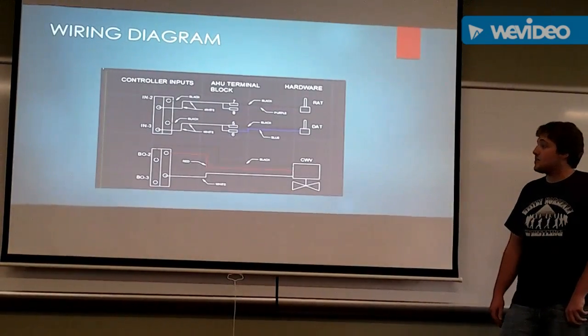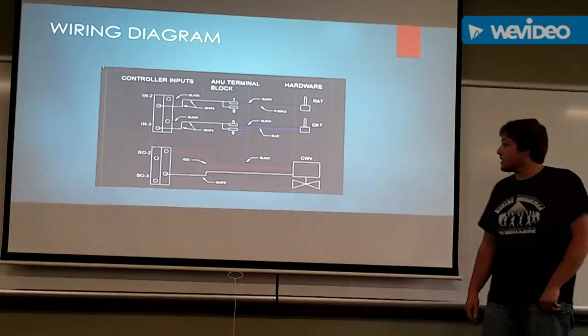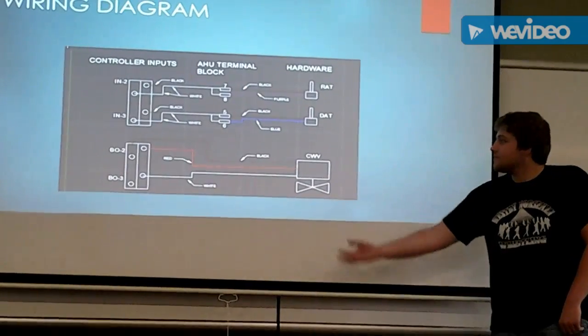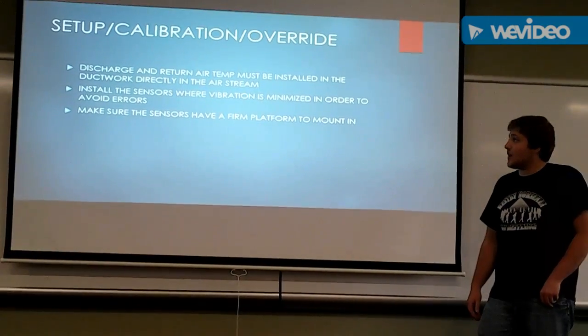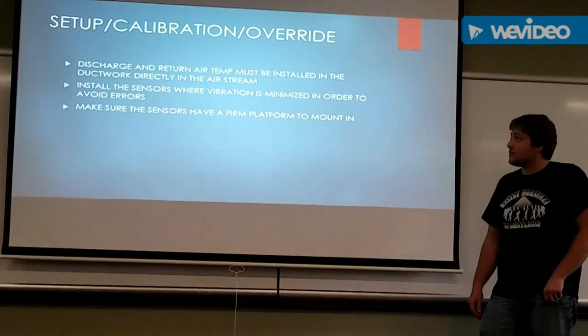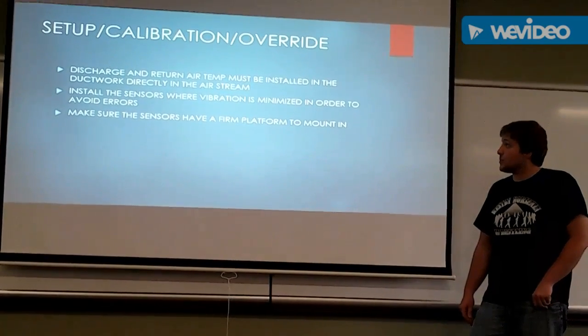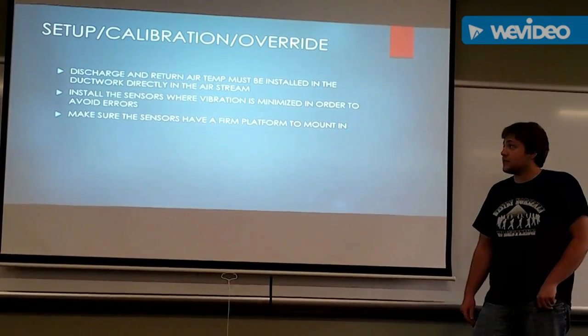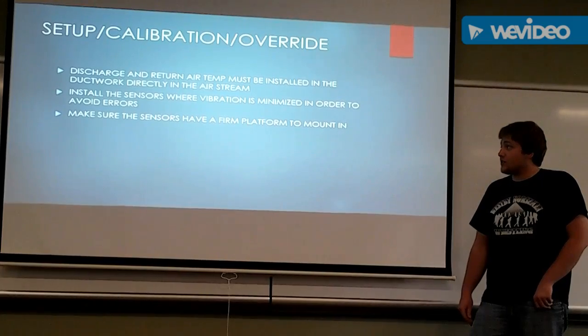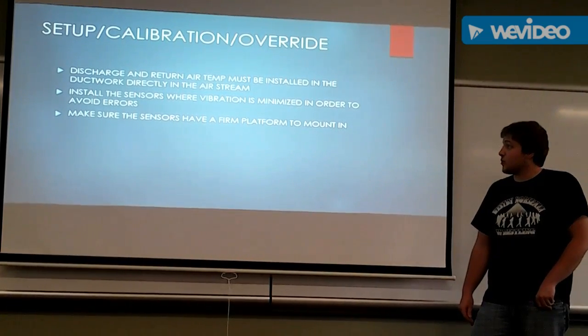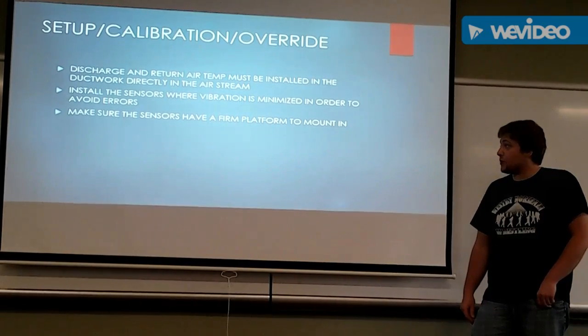This is the wiring diagram that Josiah drew on CAD. Setup, calibration, and override. Discharge and return air temp sensors must be installed in the ductwork directly into the airstream. Install the sensors where vibration is minimized in order to avoid errors. Make sure the sensors have a firm platform to be mounted on.